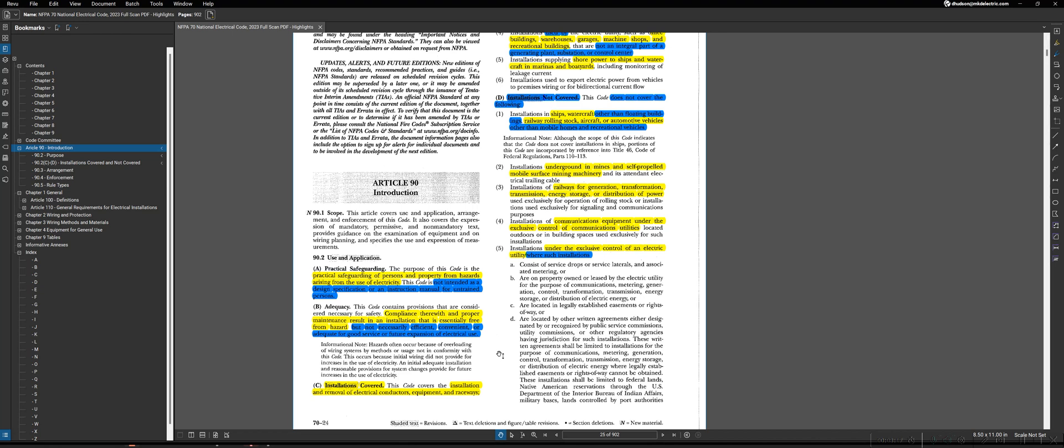For instance, one of the areas that I always point to is if we look in a commercial building, say an office, the NEC doesn't require you to install a single receptacle in an office environment. Would that be very practical for an office where it's likely that a lot of equipment such as computers or printers may be used? Obviously not, but it is free of hazard. You're not creating a hazard by doing that. Whereas, if you look in other situations, such as in a dwelling unit, the NEC will require you to install outlets spaced every so often so as to prevent the homeowner or other resident from using extension cords or doing other things that could create a hazard.